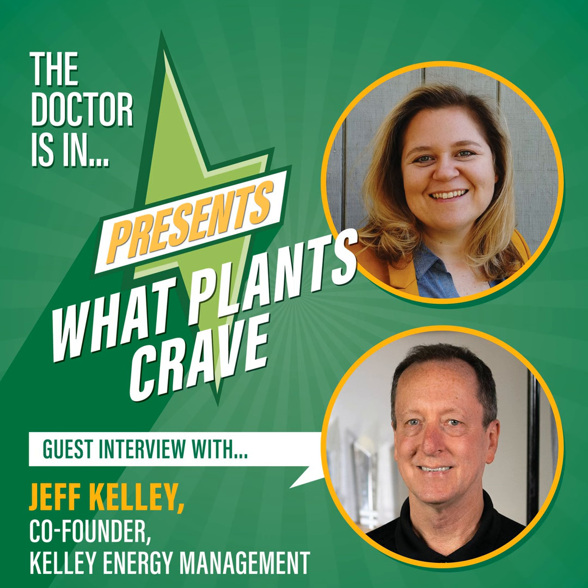Occasionally, building shell can become an issue. What I've learned indirectly is that most flower rooms are big ice coolers that have air conditioners in them. In other words, the heat can't get out. I had a guy one time say, make that back wall R30 and tell me what it does. I said, well, your bill went up by $400 a year when you did that. The heat flow is out, it isn't in. So in the summer, there's hardly any heat getting in. Most of these indoor grows don't really have a lot of skin load, and when we do the load part of our calculation, we're not seeing much there.